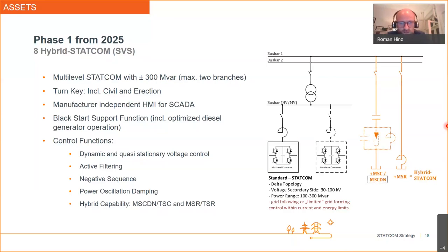The same is true for negative sequence control. If there's a contingency, for example a phase to ground fault in the grid or a two-phase fault, the STATCOM will inject an asymmetrical current into the grid, so a negative sequence current. In our first STATCOM, this was not implemented. So when there was, for example, a phase to ground fault, the STATCOM injected a symmetrical current into the grid, which was not the optimal condition for us. But with our experience from our current STATCOMs, those kinds of control schemes are already in place.